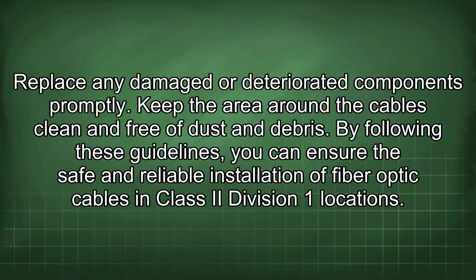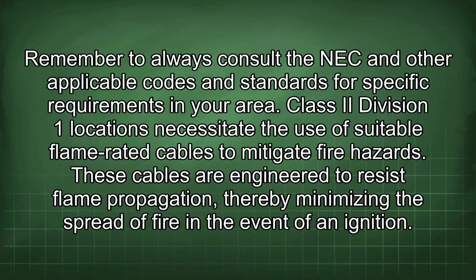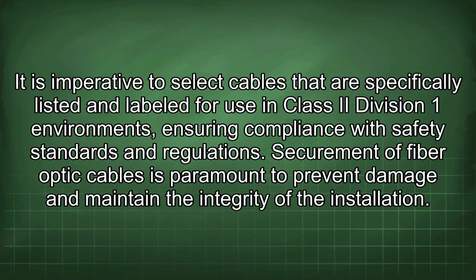By following these guidelines, you can ensure the safe and reliable installation of fiber optic cables in Class Roman 2 Division 1 locations. Remember to always consult the NEC and other applicable codes and standards for specific requirements in your area. Class Roman 2 Division 1 locations necessitate the use of suitable flame-rated cables to mitigate fire hazards. These cables are engineered to resist flame propagation, thereby minimizing the spread of fire in the event of an ignition. It is imperative to select cables that are specifically listed and labeled for use in Class Roman 2 Division 1 environments, ensuring compliance with safety standards and regulations.